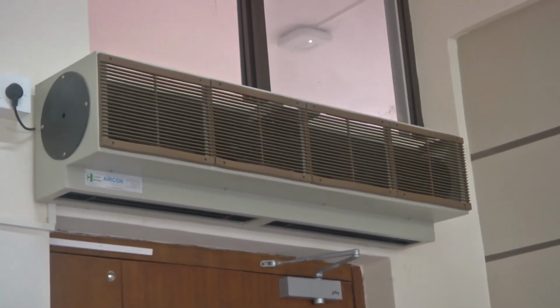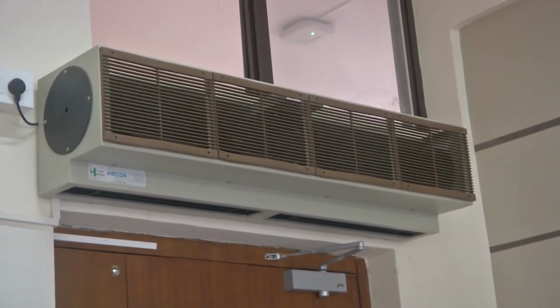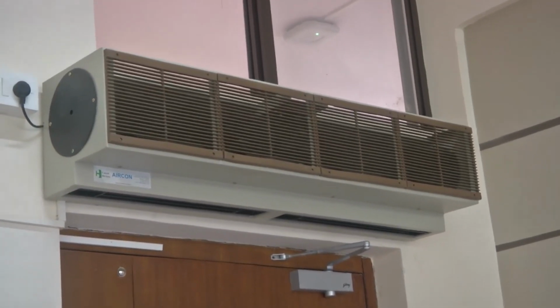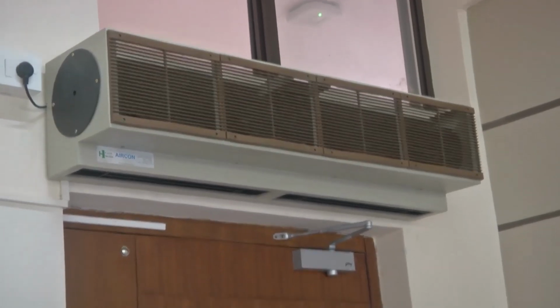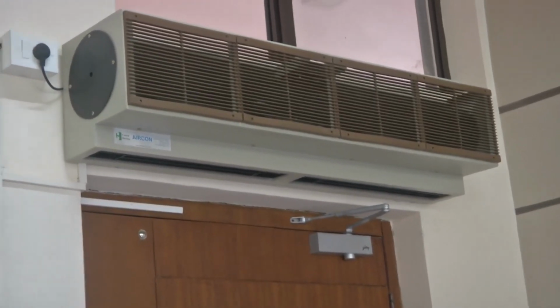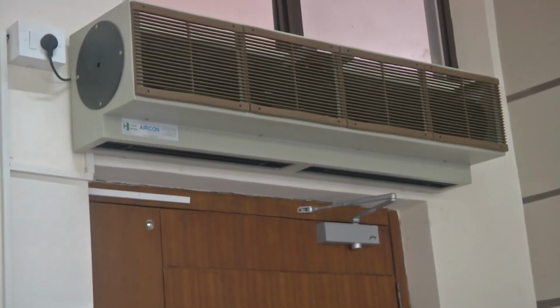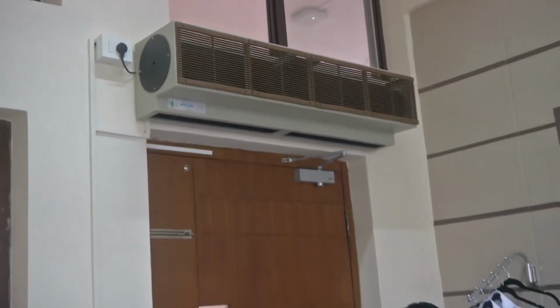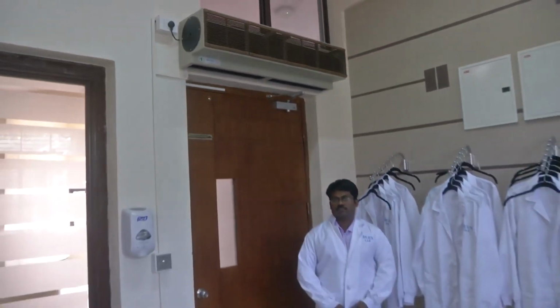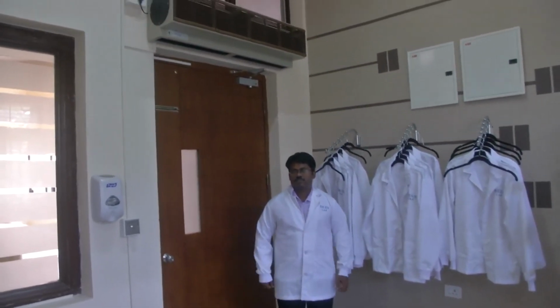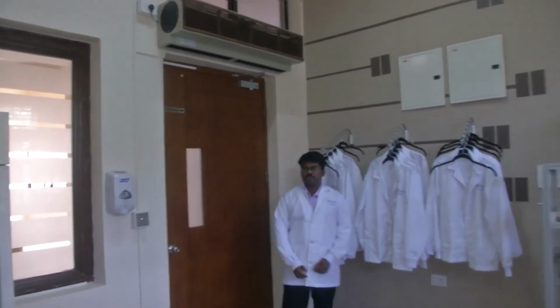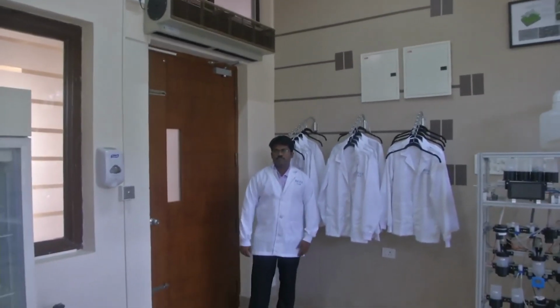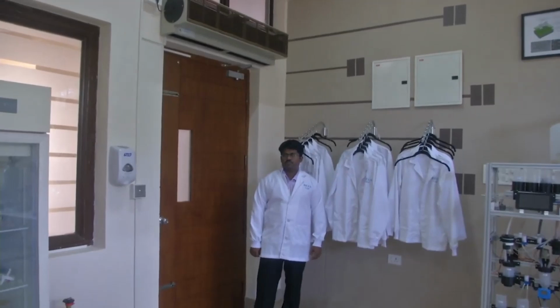restricted to that area in order to reduce any sort of contamination or particulate count or dust entering inside the clean room. We have this mechanism of flowing high speed air just at the entrance of the door. Now as soon as you give your fingerprint and open the door, the sensor there detects the entrance and then the air curtain gets activated.